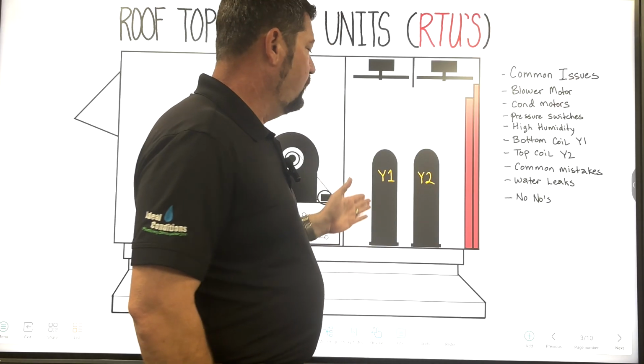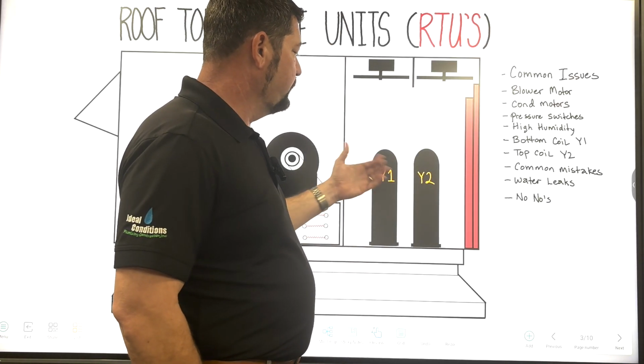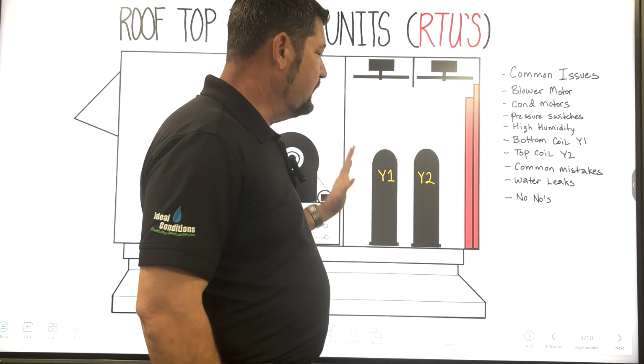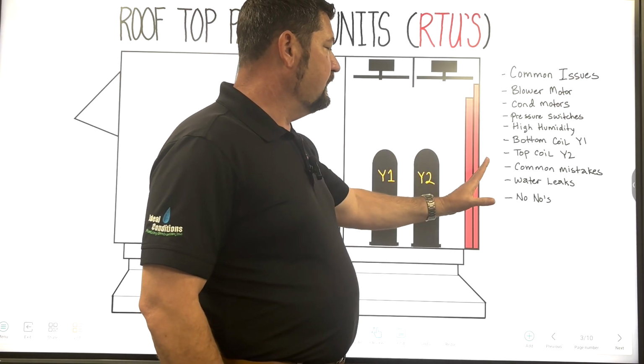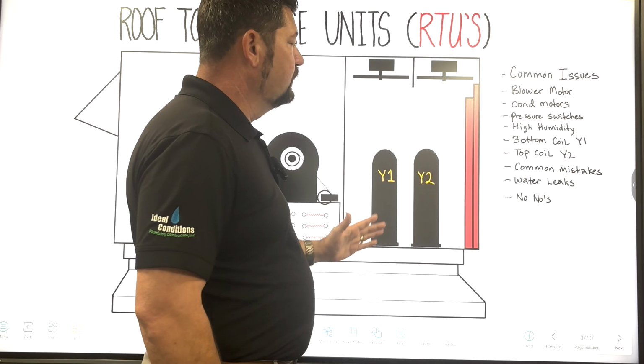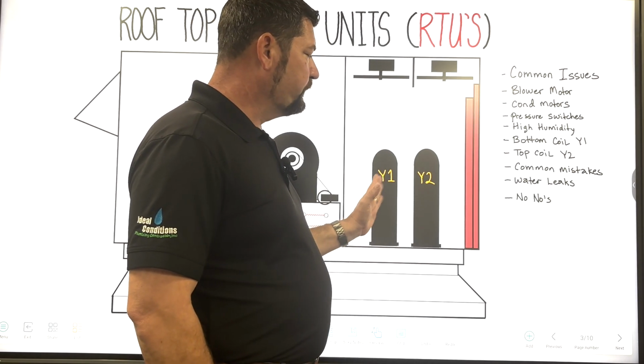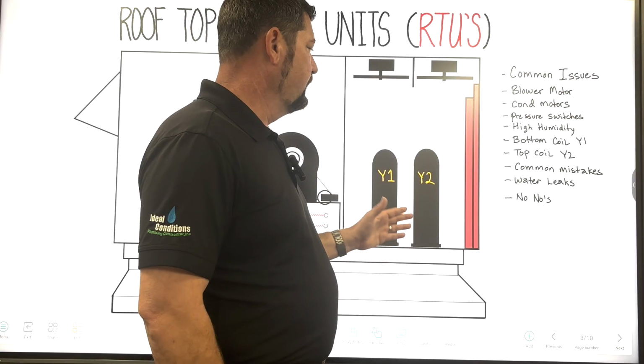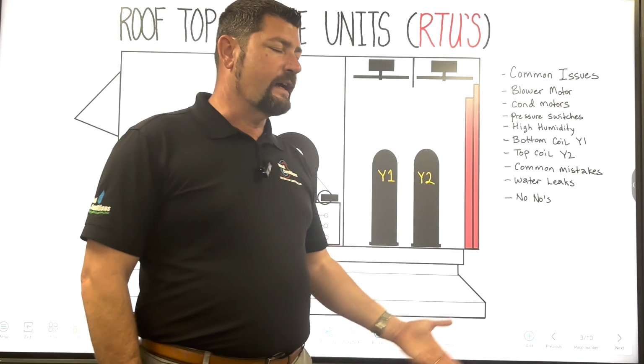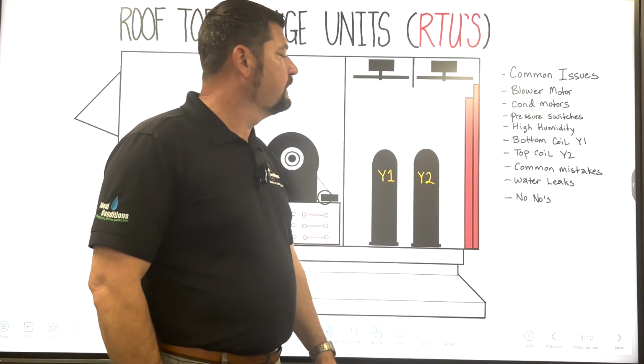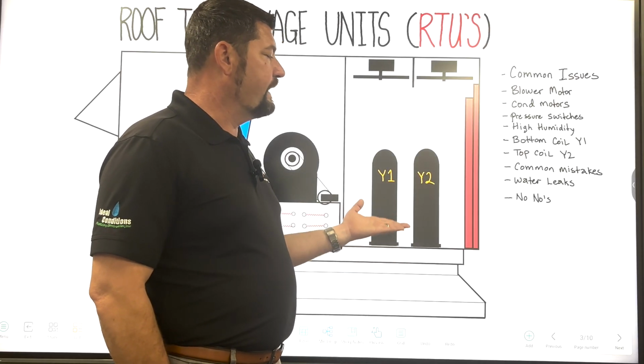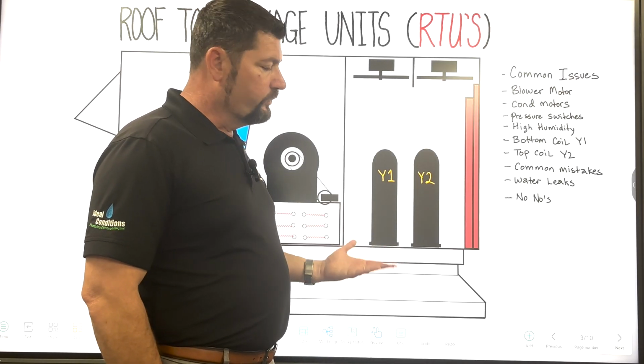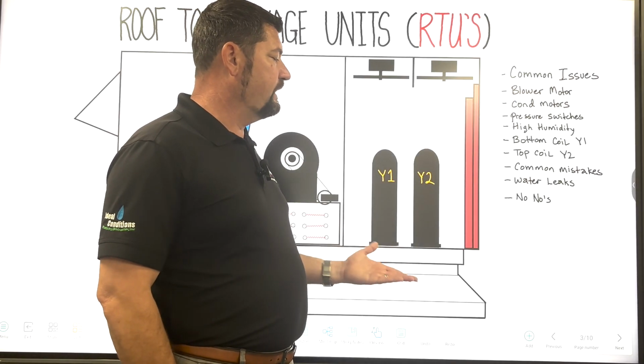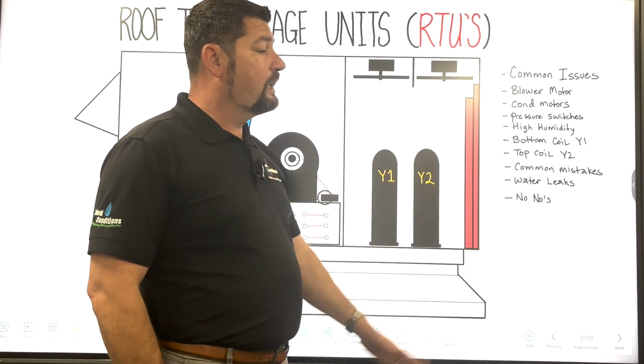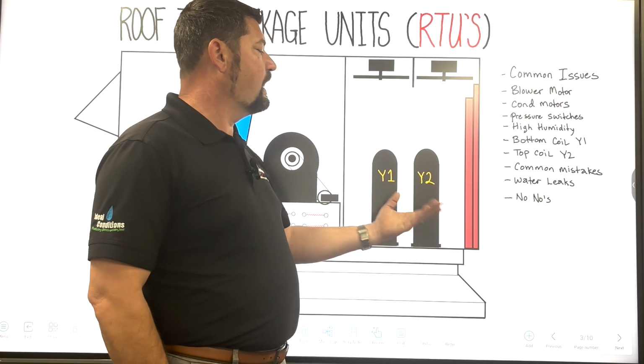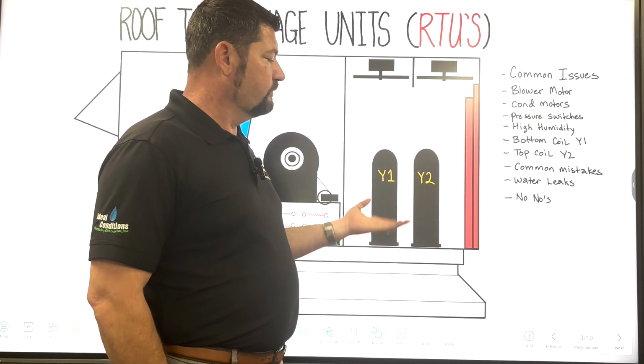Pressure switches on the compressors, as I mentioned earlier, wind up getting bypassed instead of keeping them in circuit and solving the issue that's causing the switch to go out. The most common switch that trips the most is the high pressure switch, and that high pressure switch is always one that gets bypassed. And that's something you've got to think about. Why is the high pressure switch tripping? Is the unit overcharged a little bit? Has it been worked on? Has it been serviced and had Freon added? Are these coils not clean? There's reasons why these things are tripping.